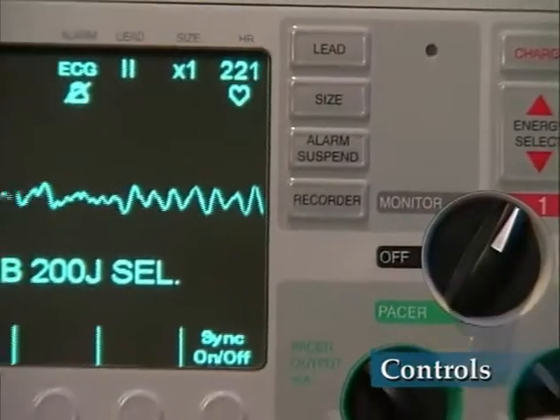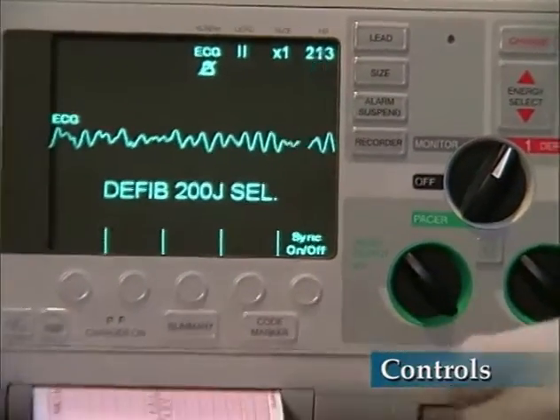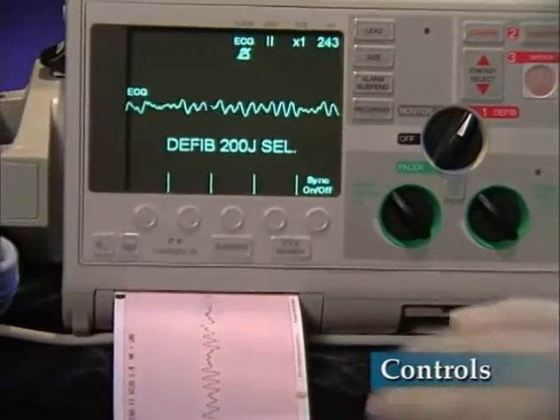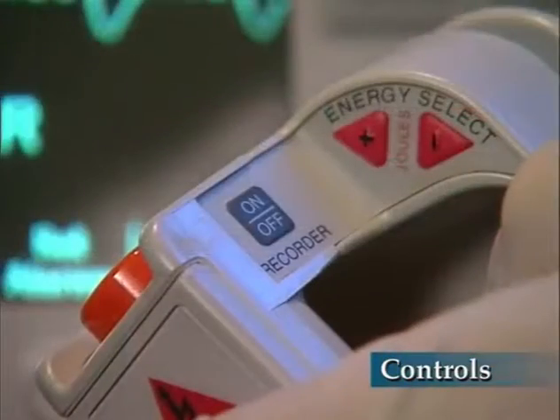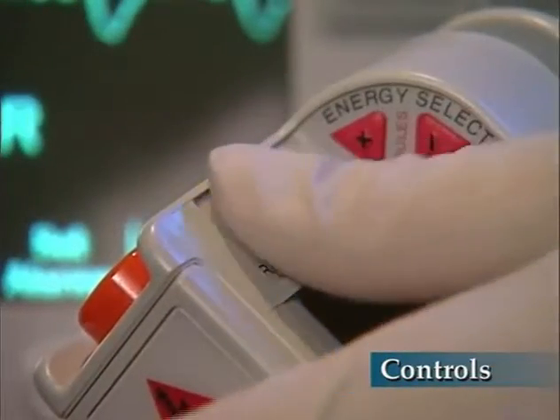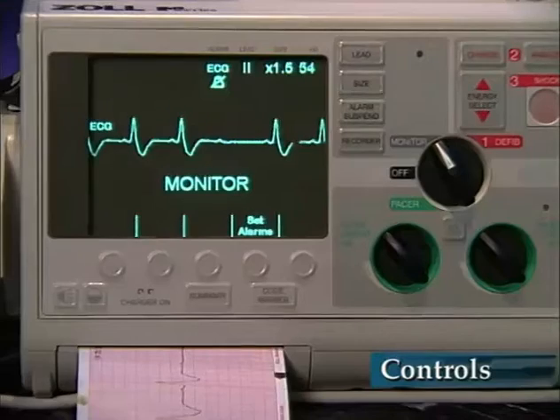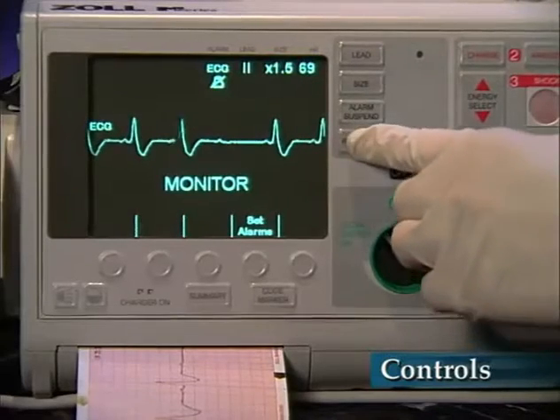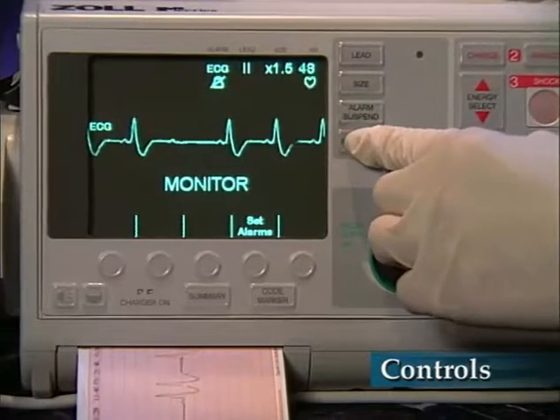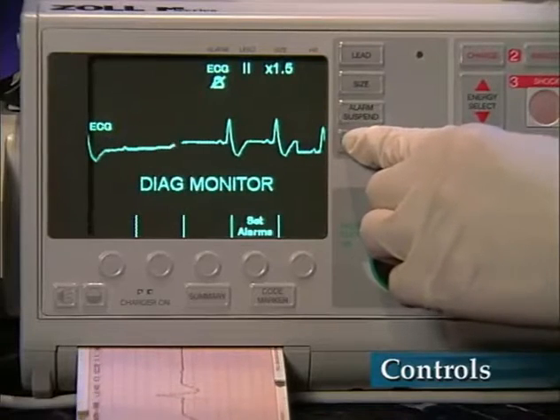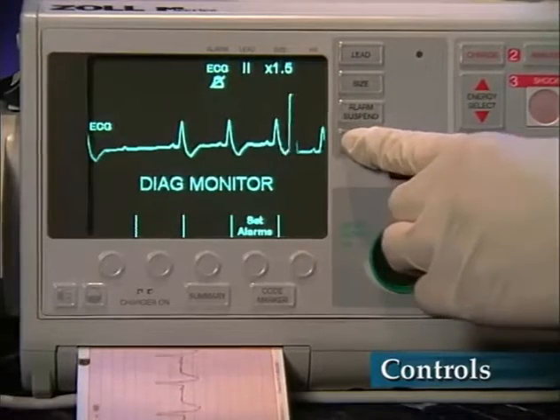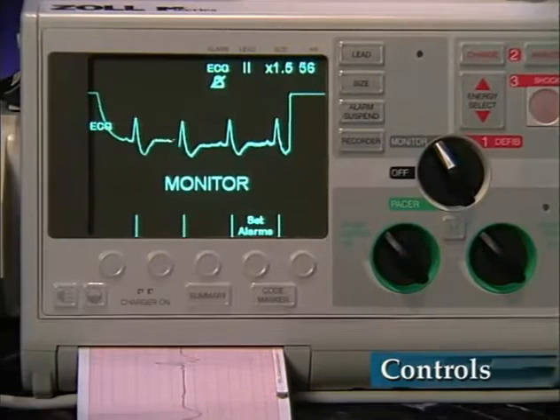The recorder button starts and stops the multiple application printer. A second recorder button is provided on the external paddles. You can change from monitoring to diagnostic bandwidth by depressing and holding the button for 4 seconds. The unit reverts to monitoring bandwidth when the button is released.